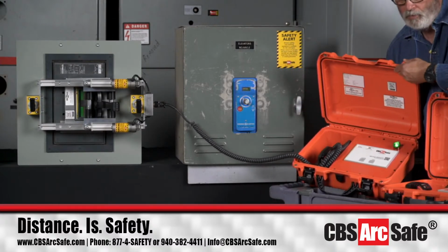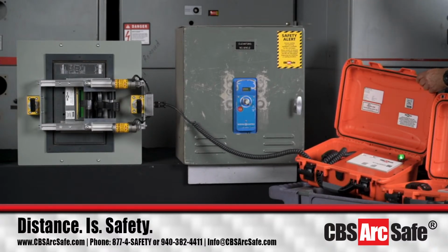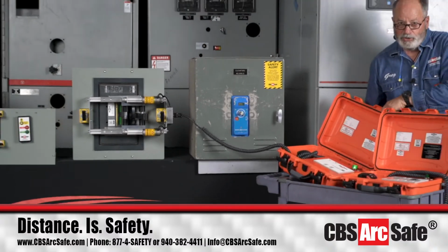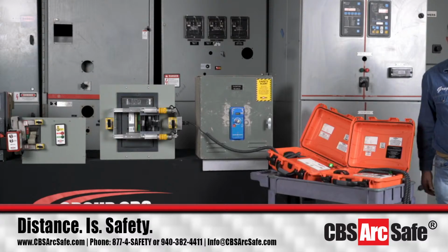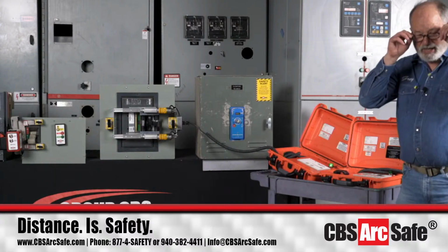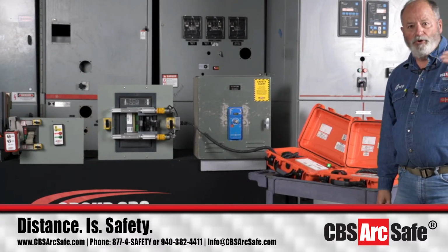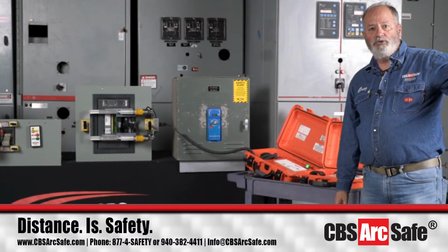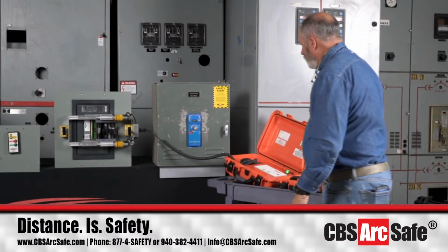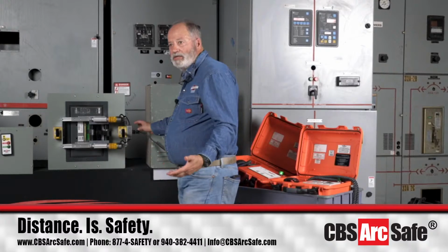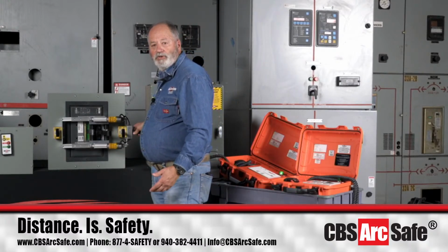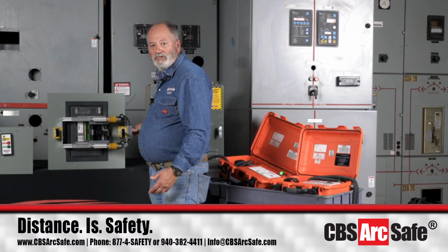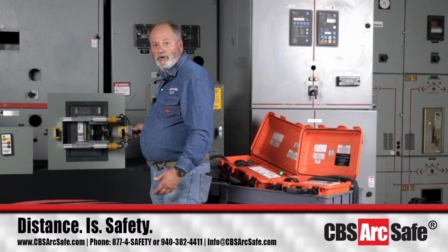When we develop an actuator for something this big, you'll notice that it takes two linear actuators to operate, just because of the sheer amount of force and the speed with which the breaker has to be moving to get all three phases to close at one time. We do a lot of testing on this stuff to make sure that as we build something, it's going to work as desired for you, the operator in the plant.